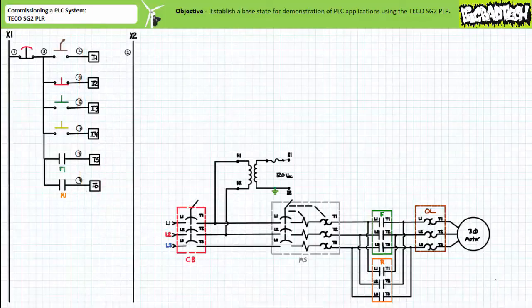This is to imply isolation between the field input devices and the PLC exists, and that the PLC program assumes responsibility for all incoming transmissions from this point on. Wire numbers can be used to further clarify points of connection. Note wire 3 is not a single wire, but rather the pooled connection of all upstream terminals of field input devices intended to operate at 120 volts AC.